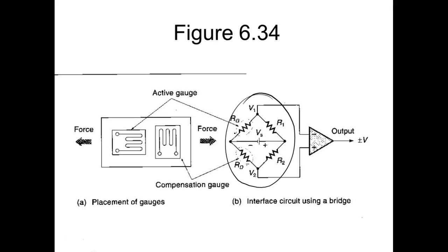So I don't want my scale to weigh more in the summer or less in the summer than it does in the winter. So what we do is we put another gauge in there that's opposite of the force. This is the spring action, right? So what happens to the gauge of a spring when you stretch it out? The gauge doesn't change and the length doesn't change. So one of them acts as a spring action, one of them acts as a gauge, and they're mounted right by each other. So if the temperature goes up, the resistance goes up here, and the resistance down here goes up exactly the same amount. It's the same gauge made out of the same material, the same length. Everybody understand that?